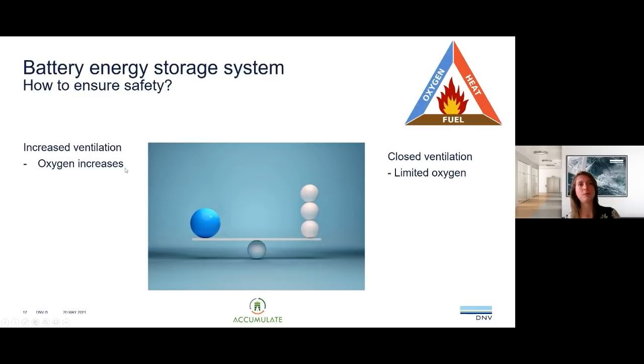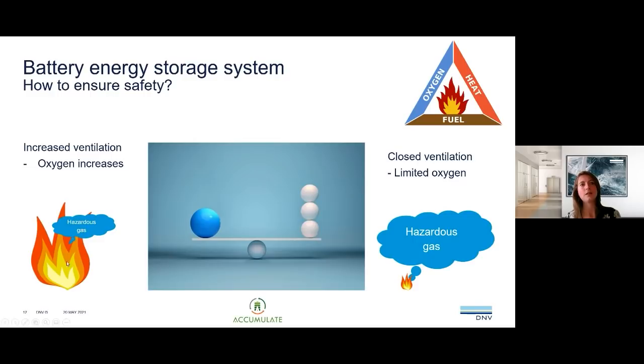Yes, there is indeed a balance between increasing ventilation and closing off - between the explosion risk and the fire risk. On one hand, if there's an enormous fire, if we increase ventilation, the oxygen is increased and a lot of hazardous gases are released, so we get a huge fire. On the other hand, if we limit the fire by limiting the oxygen, the hazardous gases can accumulate and you get explosion risk. So in your safety strategy, you need to balance between the two.